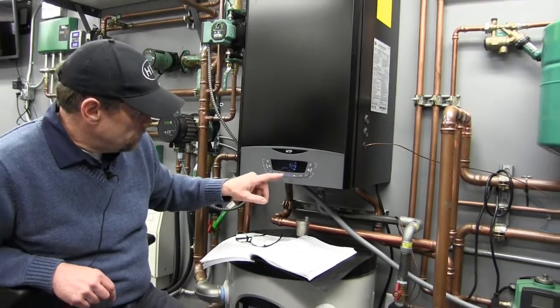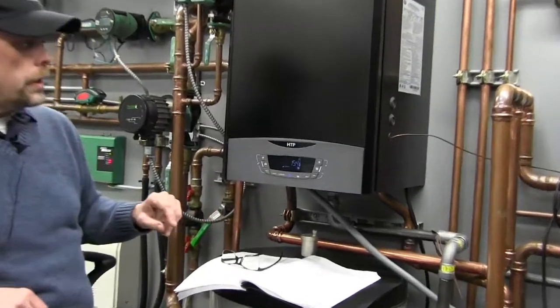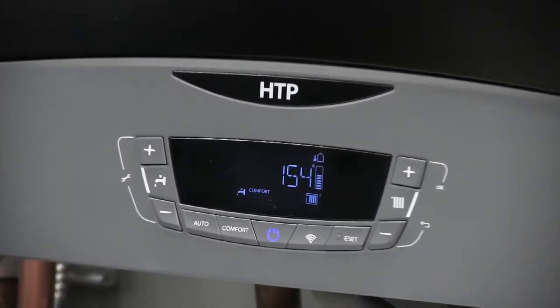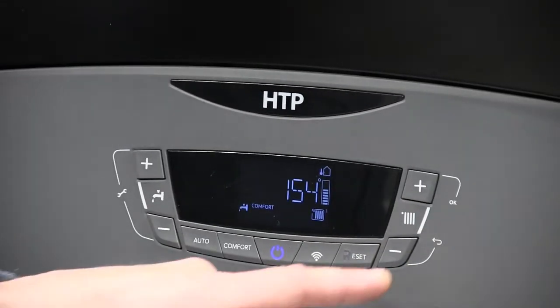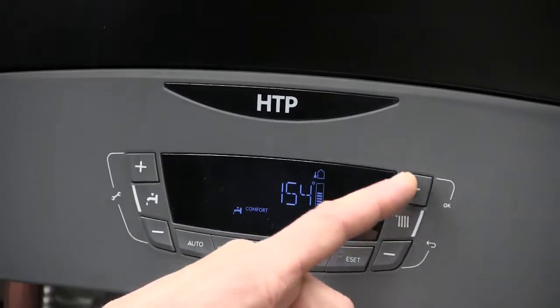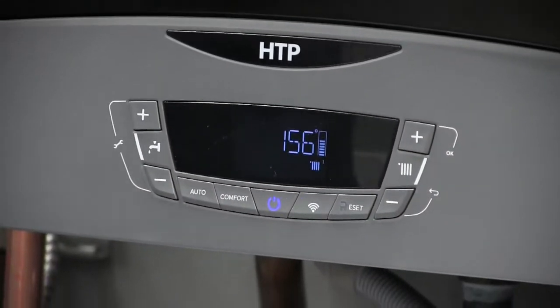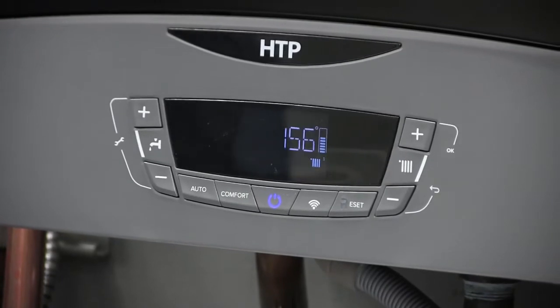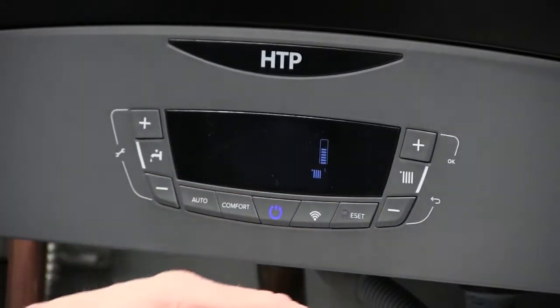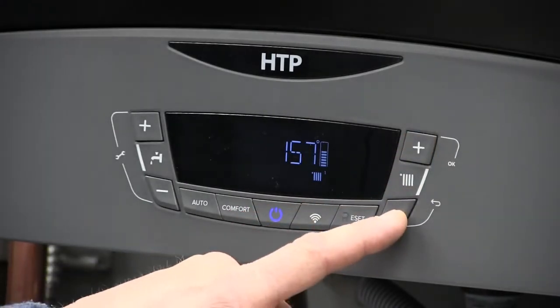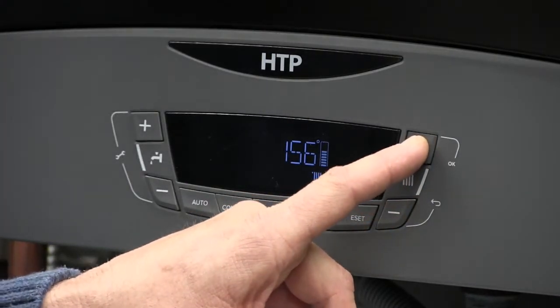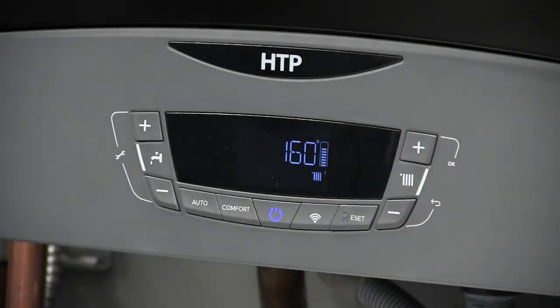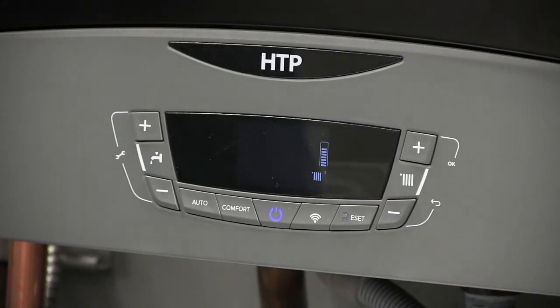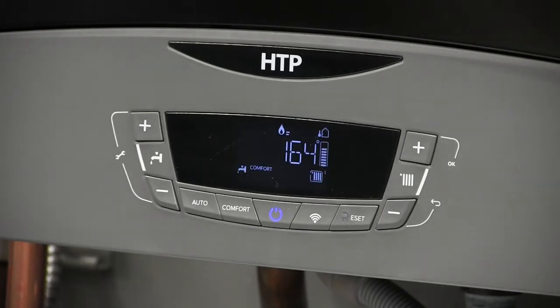So currently, well, let me put it back. Currently, I am in set point operation. So by hitting either one of the plus or minus buttons on the right side, it'll tell me what my actual set point temperature is. And in this particular case, the set point temperature is 156. While it's blinking, I have the ability to raise or lower that set point temperature, and this is a permanent change. So perhaps I want to set it for 160, and it will stay at 160, and that will be my set point operation. Now, if we're utilizing outdoor reset strategy, it's going to function a tiny bit different.